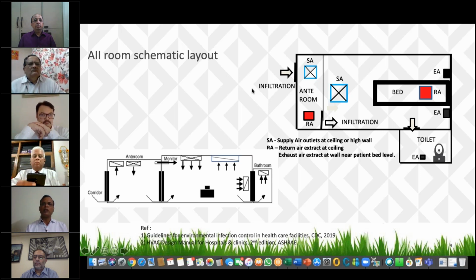So we can convert a regular air-conditioned patient room into a once-through, non-recirculatory system. Convert it into negative pressure, maintaining about 12 air changes per hour minimum, and about 2.5 Pascals minimum as the standard demands, but practically we would need at least -5 Pascals or more. Treatment of exhaust air should also be considered, since it could carry viral-laden droplets. These are the possibilities to convert a standard room into a COVID patient room.